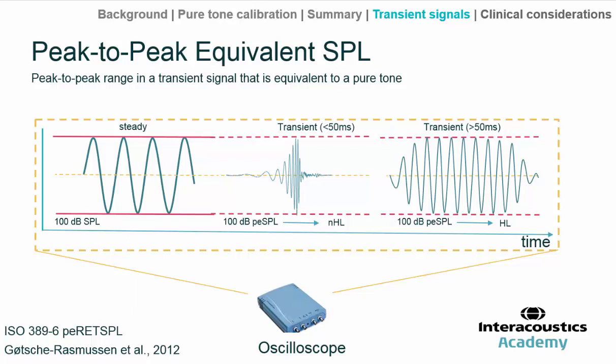With ISO 389.6, in theory we shouldn't be using the label NHL — we should be using HL. It's slightly incorrectly labelled as something of a hangover from a time when these international standards weren't available. But having continued in the use of NHL somewhat inappropriately, at least it gives us an easy distinction to show that we're talking about a stimulus of very short duration — less than 50 milliseconds as a rule of thumb.